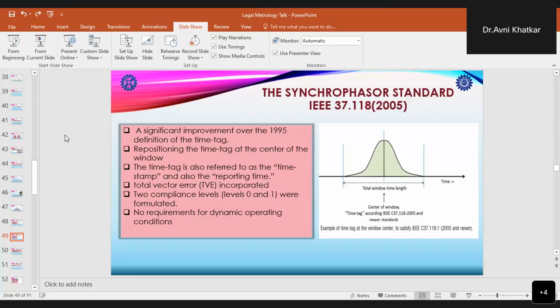time. In this 2005 standard, along with this center of the window time tag or timestamp, also known as the reporting time, the notion of total vector error, that is TVE, was also incorporated in order to evaluate the phasor measurement requirements. And two compliance levels, that is level 0 and level 1, were formulated in order to assess measurement accuracy over a range of magnitudes, frequencies, and phase angles. However, the main shortcoming of this standard was that it did not include any requirements for dynamic operating conditions, and hence it could only be applied to steady state conditions.